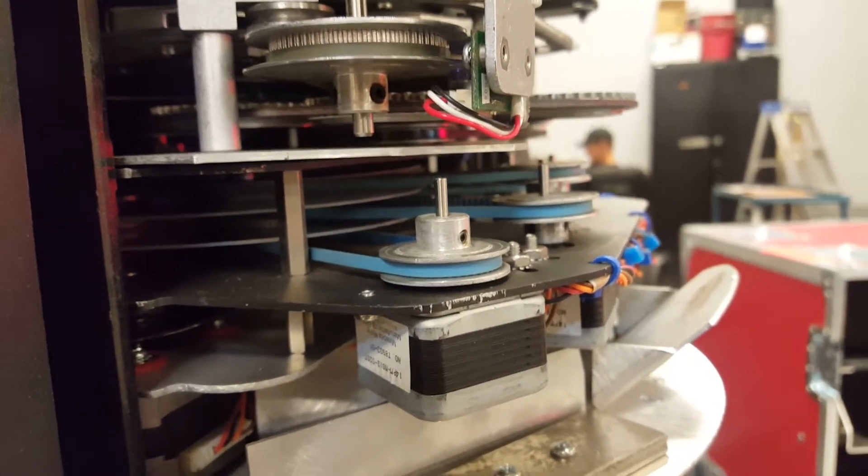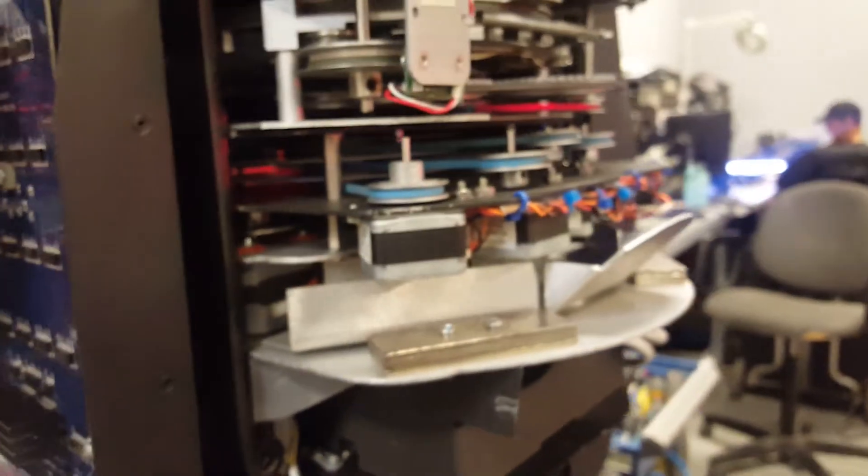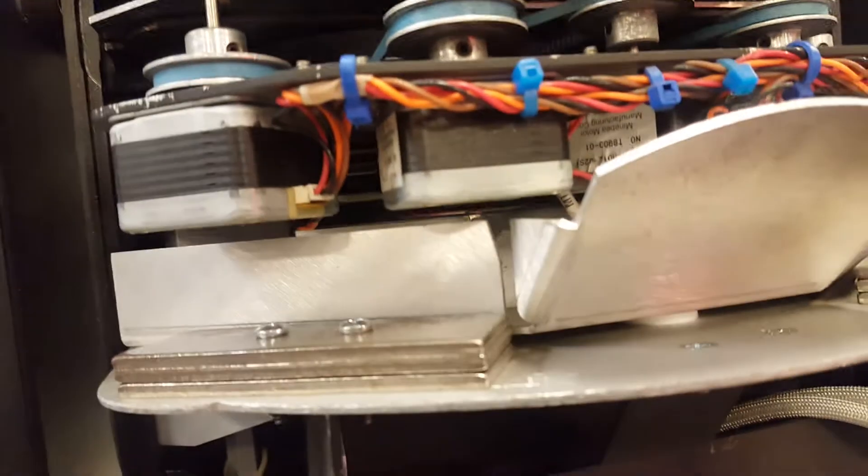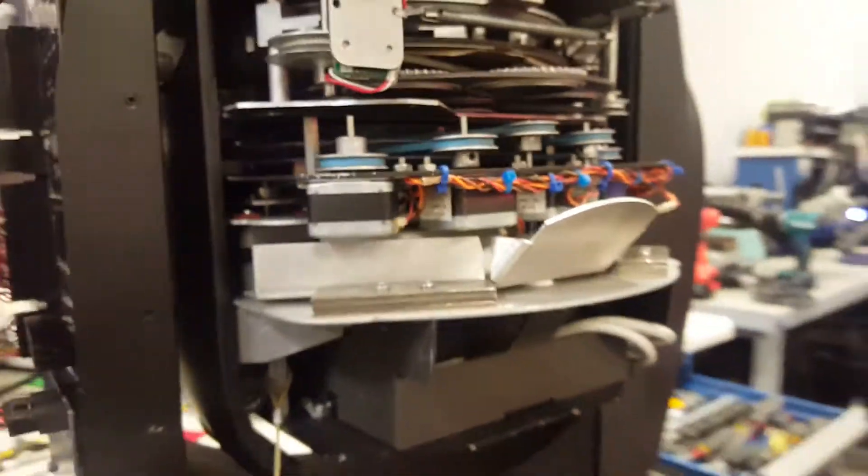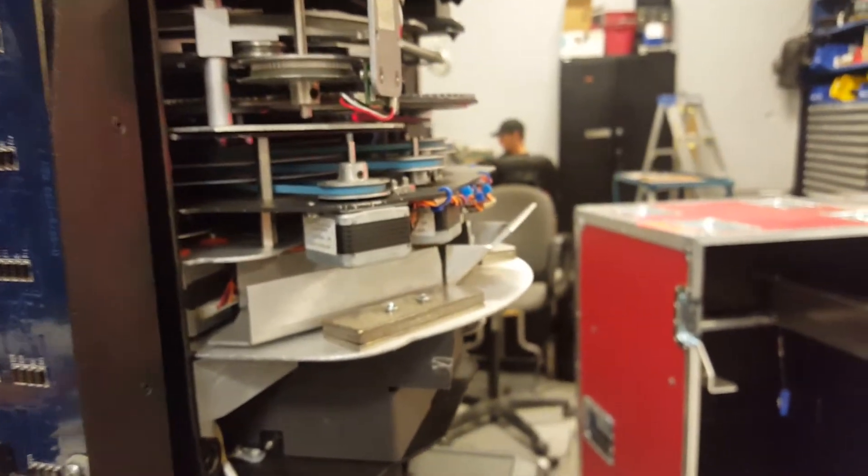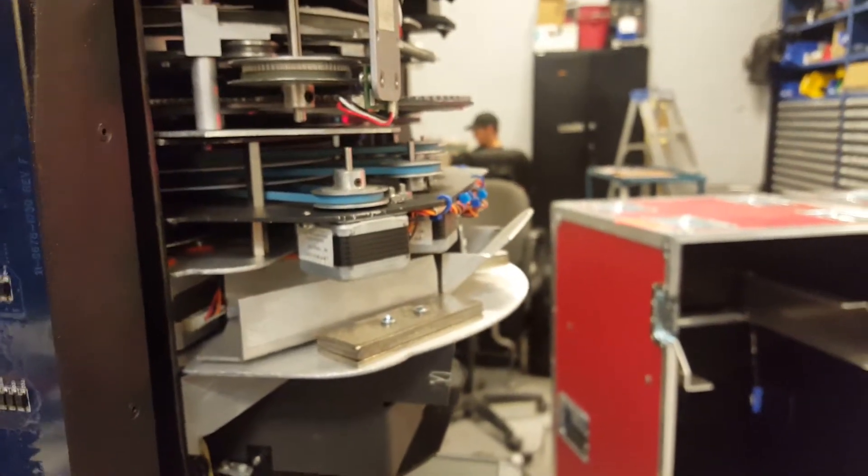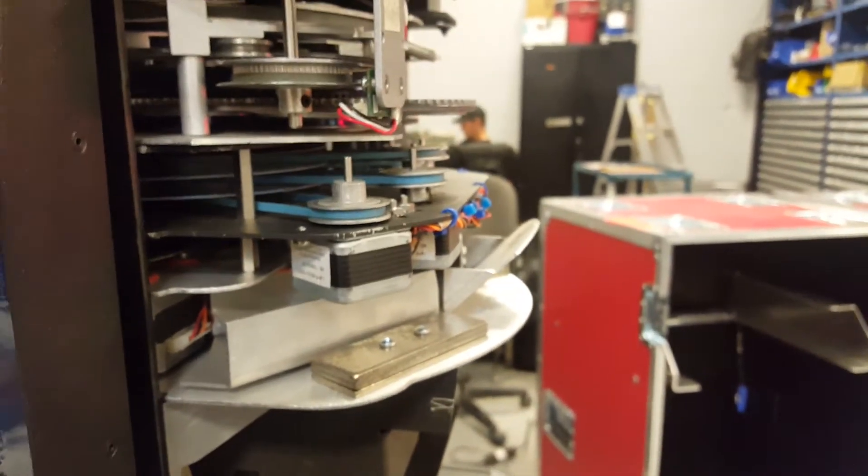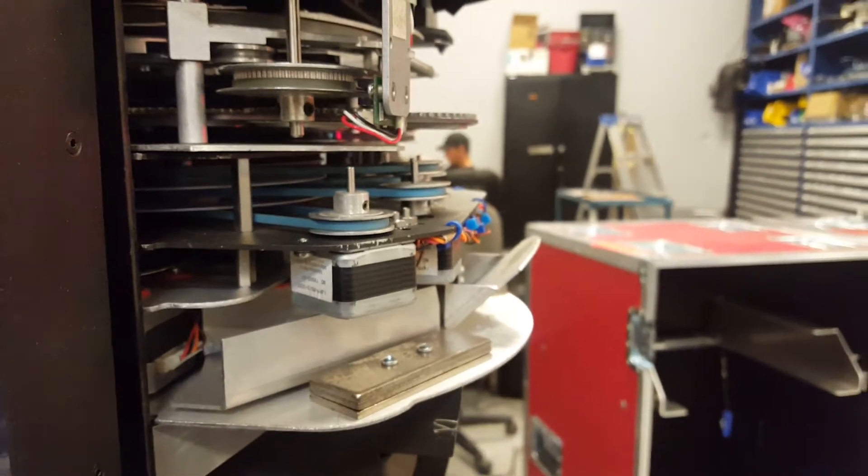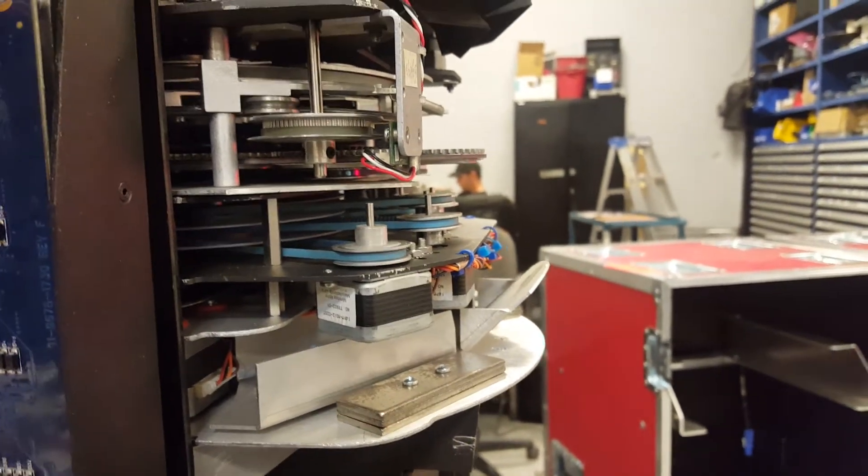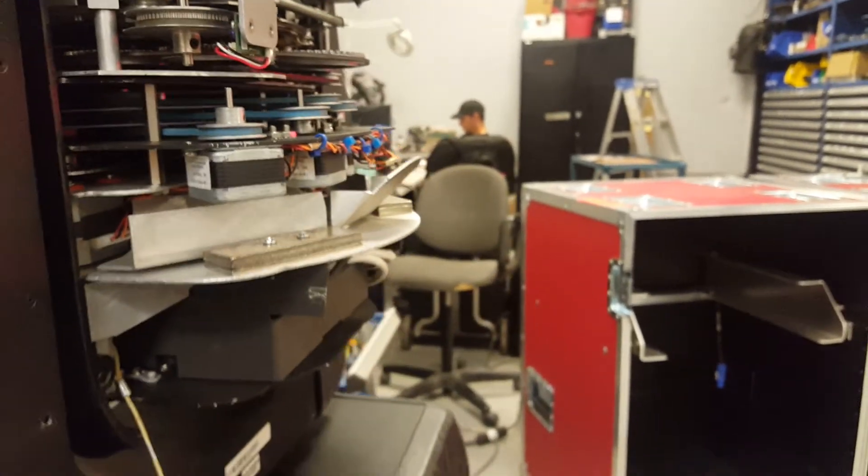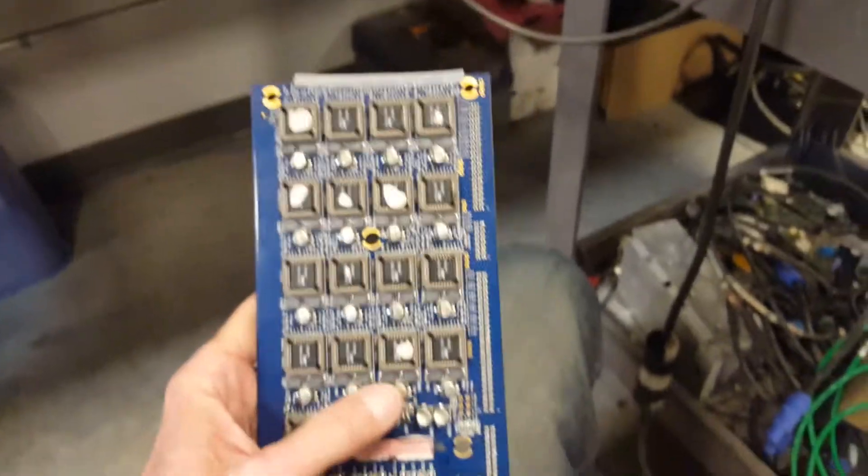Usually you probably look at this and if the connections are okay, you'd say you have to replace the driver, that the driver's blown. And you'd be right because it is a driver problem, but at the same time in this case the driver is not dead. It's just that these boards are fairly old and now they're getting a little loose, maybe some dirt getting in the contacts.